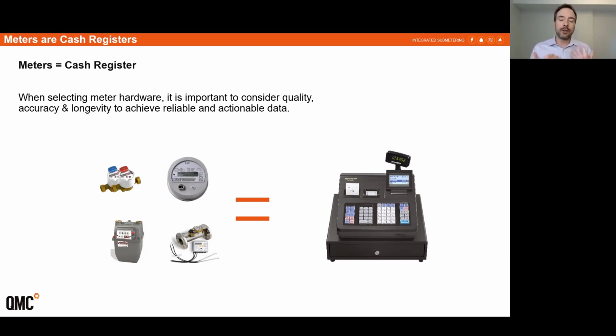So again, we need to remember that the primary function of a meter is a cash register for billing purposes. That's why there's a lot of regulations and restrictions on what you can do with existing meters, so we can't just tap into every existing meter in the field. It's often needed to be protected as a measurement and billing device first, so we need to be conscious of that when designing and interacting with existing meter systems.